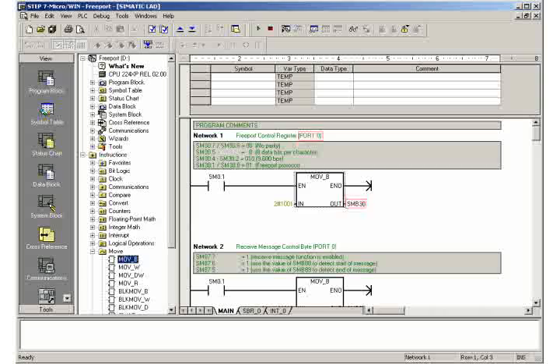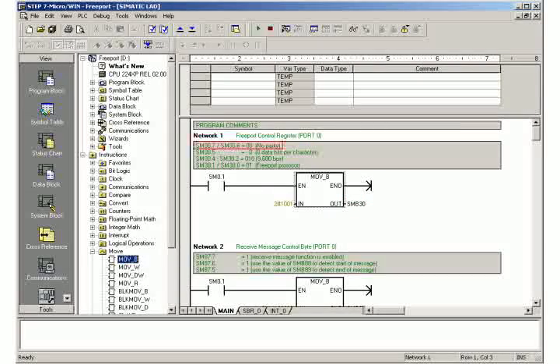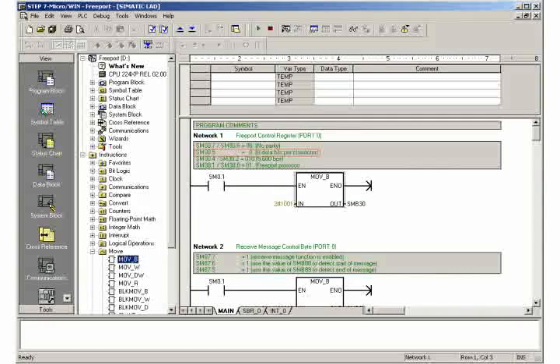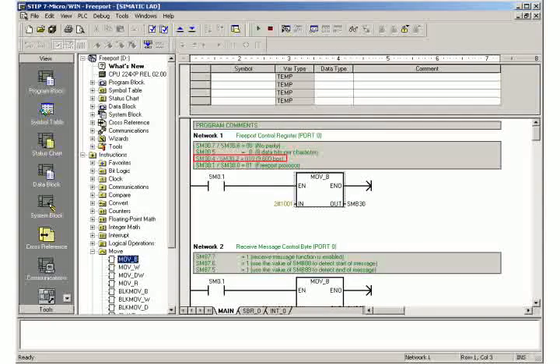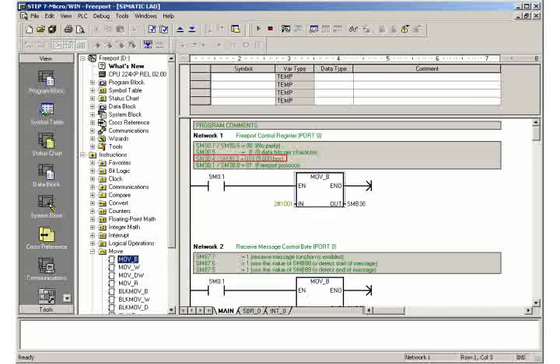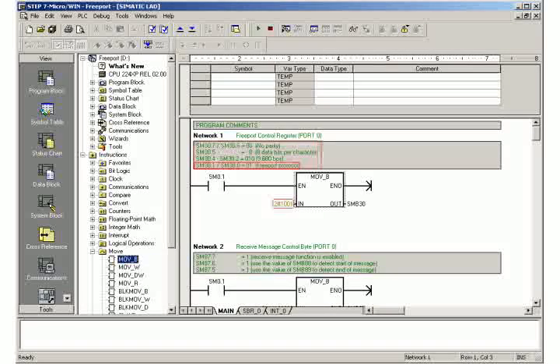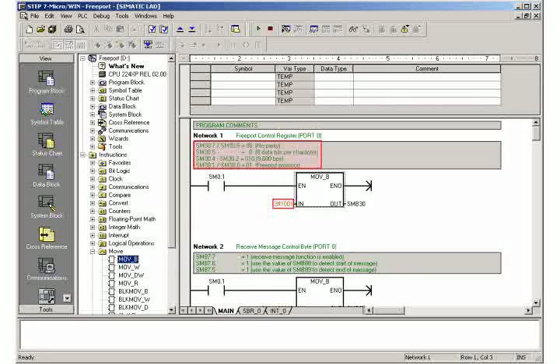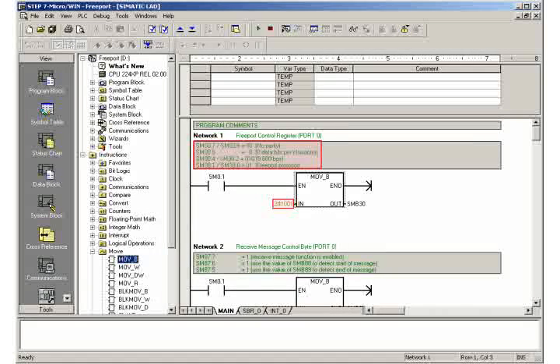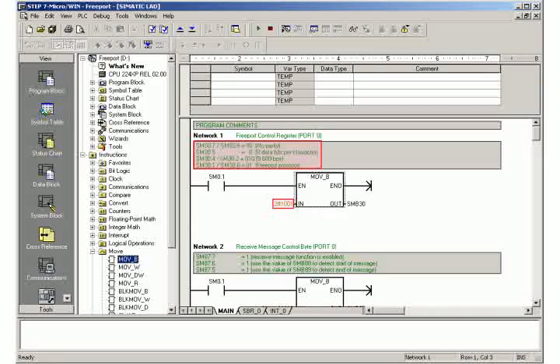Select the following settings: no parity, 8 data bits per character, 9600 bits per second, and activate the free port communication protocol. These settings are later adopted for the RS232PPI multi-master cable as well as in HyperTerminal.